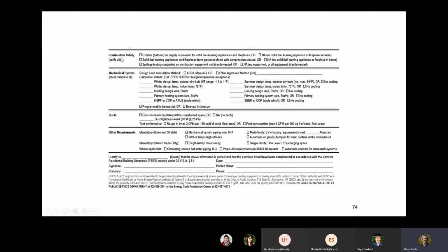Yes, I did this. Yes, I did that. For the mechanical system, the design load calculation method, how did you do it? Did you use Manual J, which is the most common one, or did you use some other approved method? And if you did, you're supposed to put down what method you used in here. And then all of these numbers are numbers that come out of the heat load. So if you're the builder and you need to fill out this energy code certificate, you're going to need these numbers, and they come out of the heat load calc. And so you should ask your heating system guy for them.